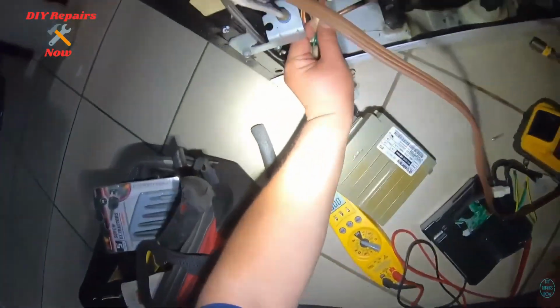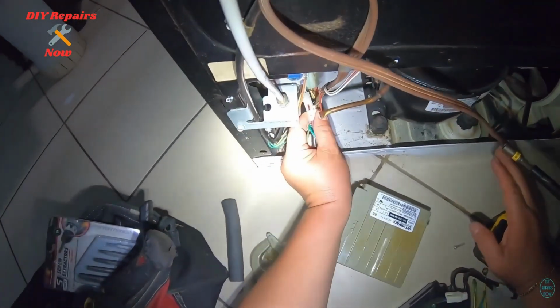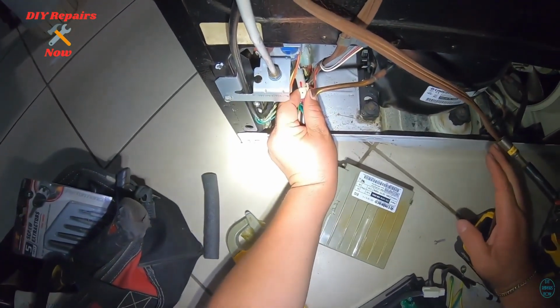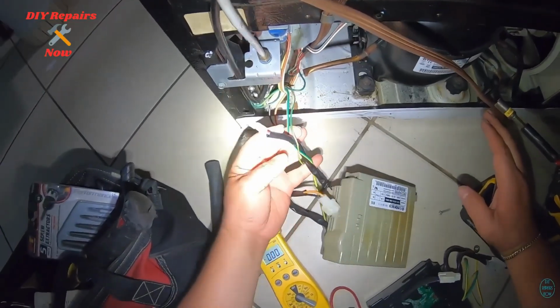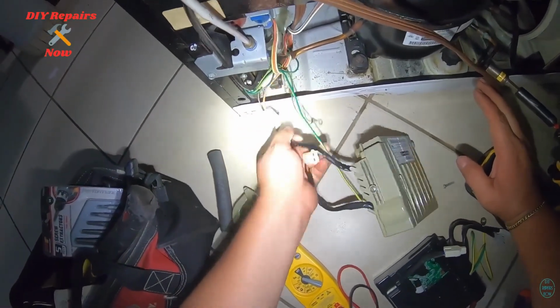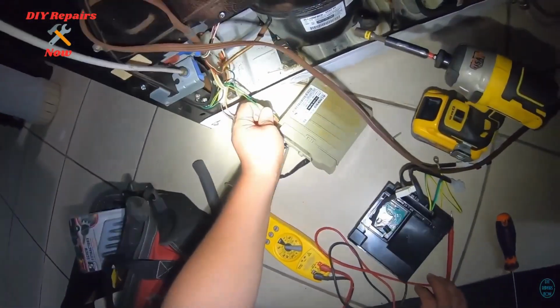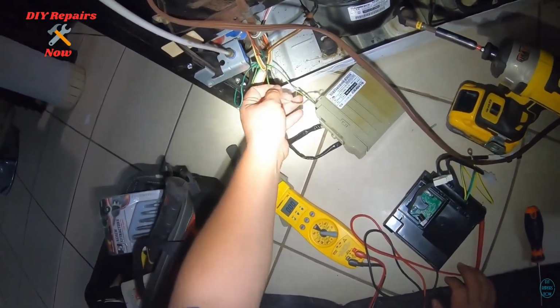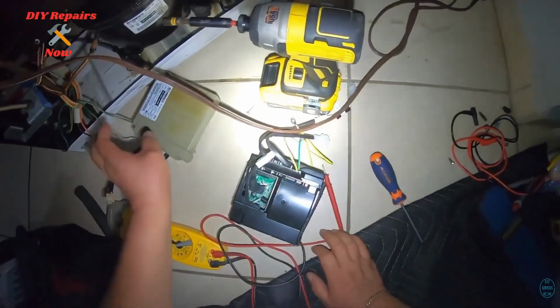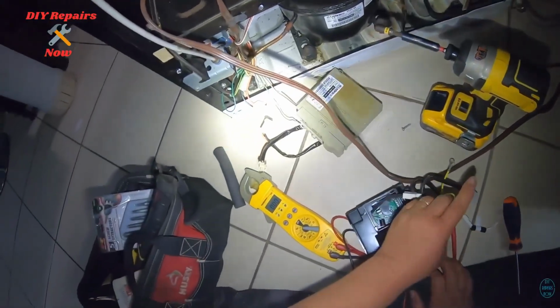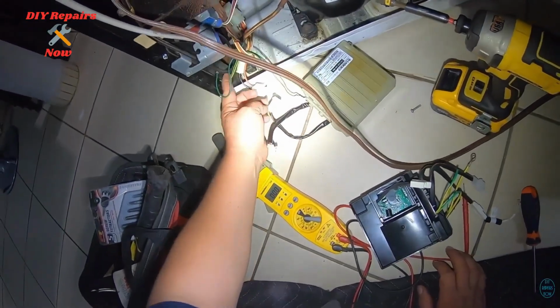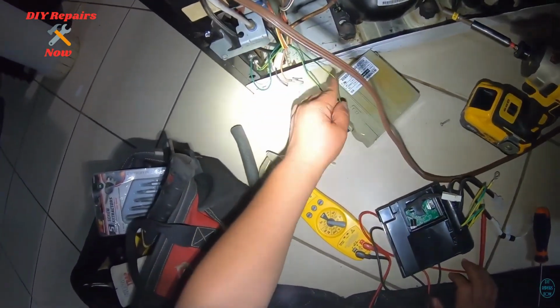With an inverter system, don't automatically assume the problem is a traditional compressor start relay. Inverter refrigerators use different compressor control technology, and the inverter board itself can be part of the starting and operating system. Another symptom: the inverter board has visible damage. Sometimes the board itself can provide clues. Look for things such as burn marks, melted components, damaged wiring, loose connectors, corrosion, a burnt smell, signs of overheating. If you see obvious damage, the inverter board should be inspected carefully.